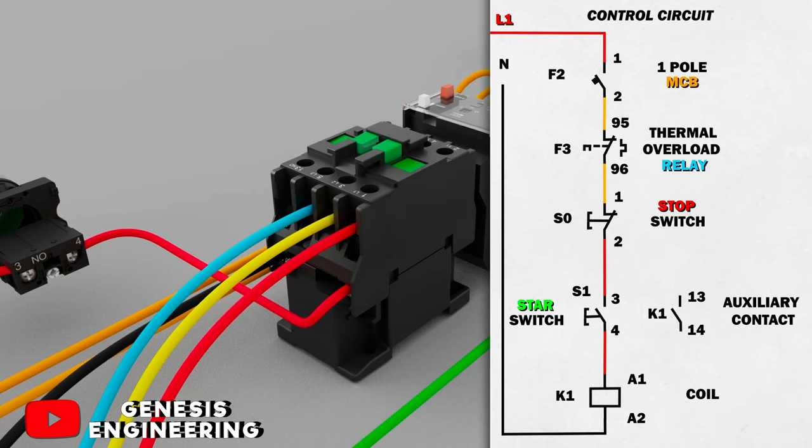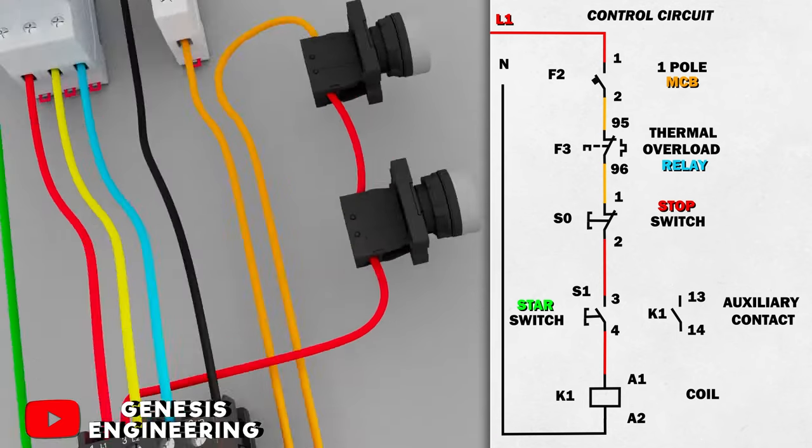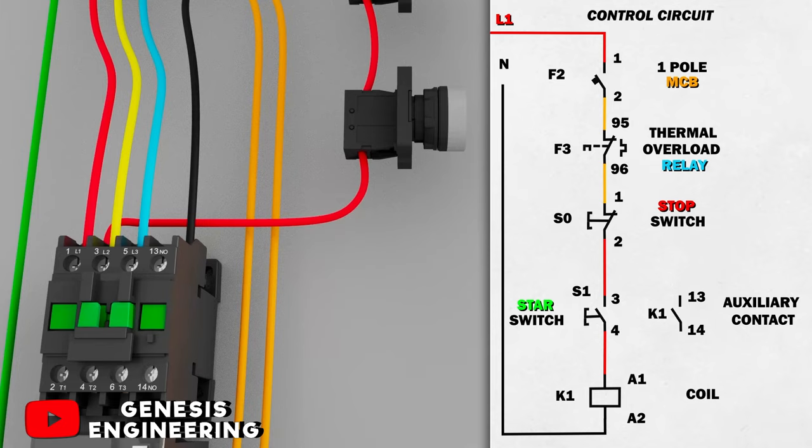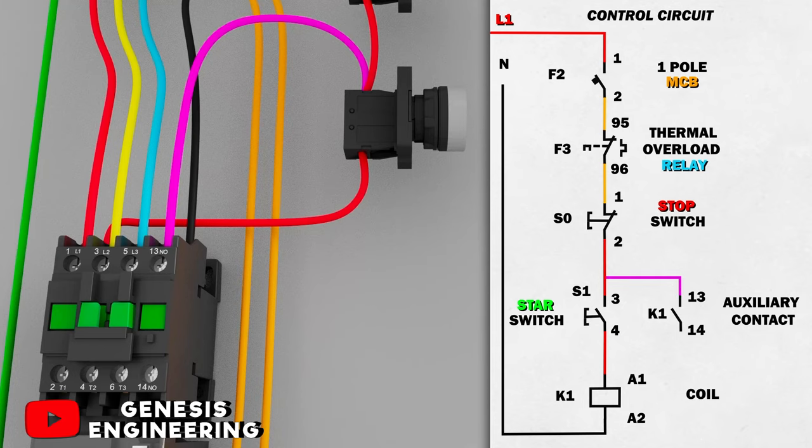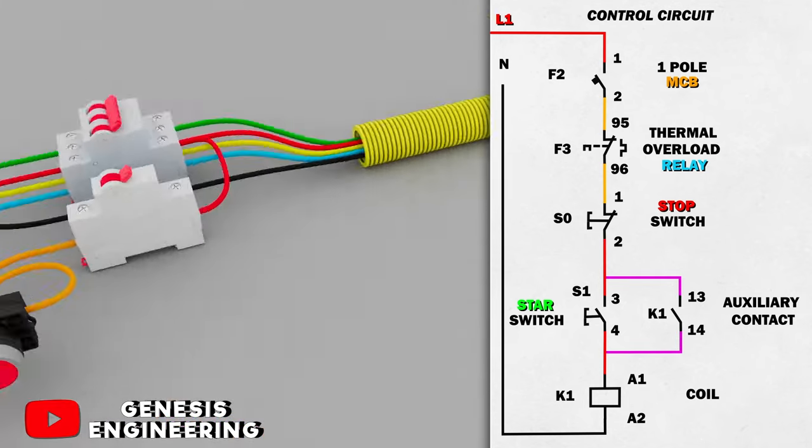Now we are going to make the holding contact. That is, we are going to connect auxiliary contact 13 and 14 of the contactor in parallel with the green button. Terminal 3 of the green button connected with terminal 13 of the contactor and terminal 4 of the button with terminal 14 of the contactor.